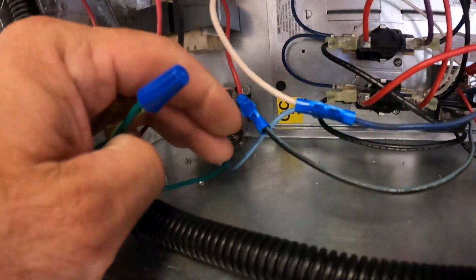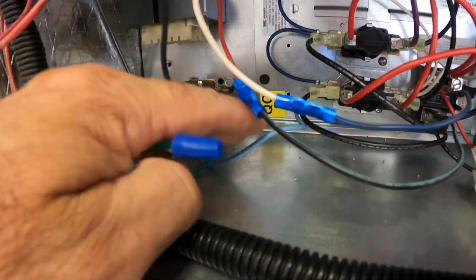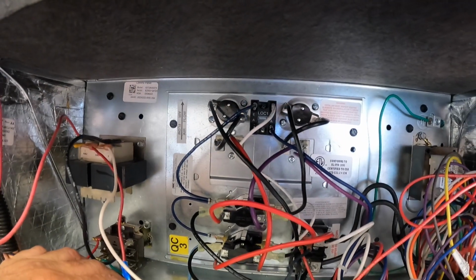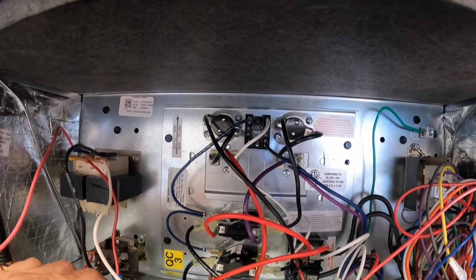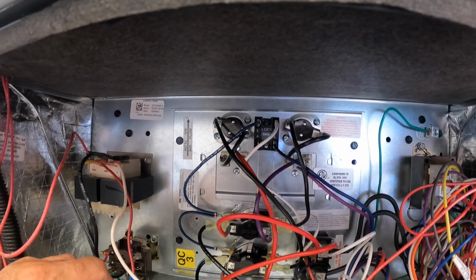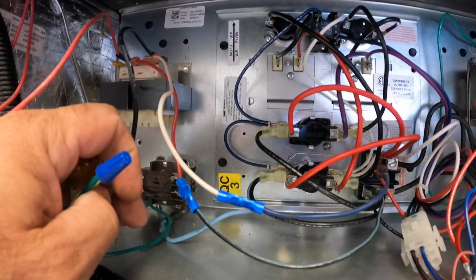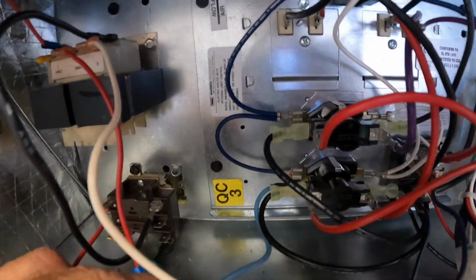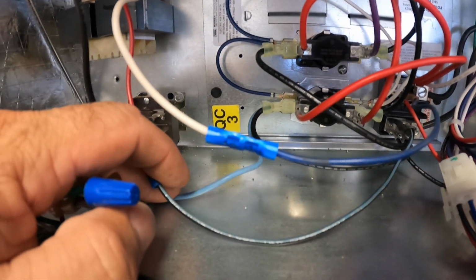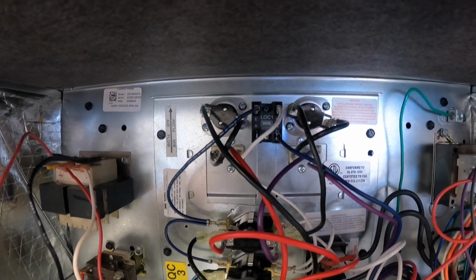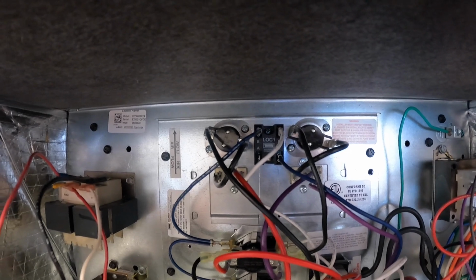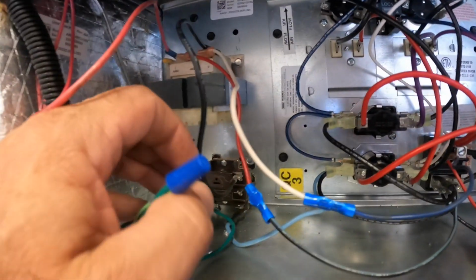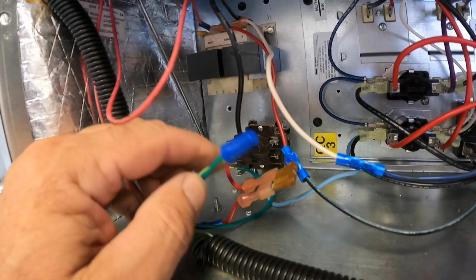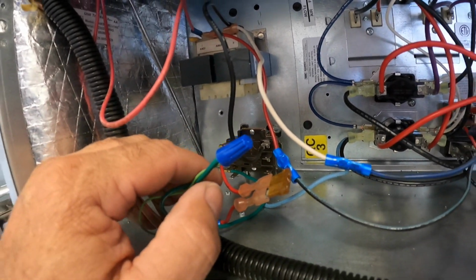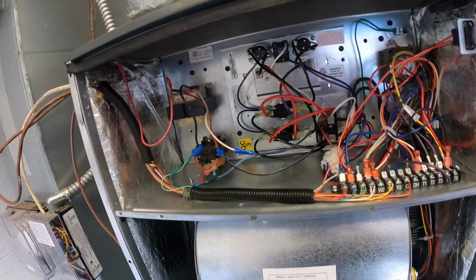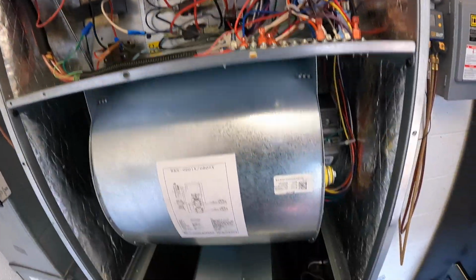I had a little short blue jumper on the truck for the common, and I got to thinking, if the electric heat wasn't working for some reason, you probably wouldn't want it sucking outdoor air in anyway. So I just jumped right off that bottom switch down there to get my common. So if the heat kit gets locked out there, it'll also lock out the air damper for a little bit too, until they reset the power or the electric system has an outage and it comes back on again.